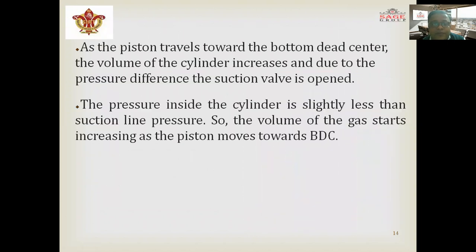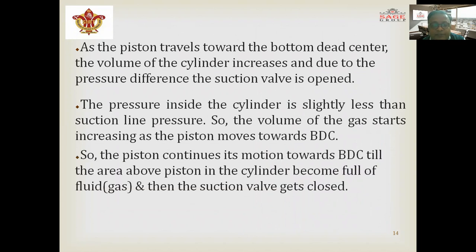In theoretical terms, as the piston travels toward bottom dead center (BDC), the volume of the cylinder increases. Due to the pressure difference, the suction valve opens when the pressure inside the cylinder is slightly less than the suction line pressure. The volume of gas starts increasing as the piston moves towards BDC. When the cylinder area above the piston becomes full of gas, the suction valve closes.